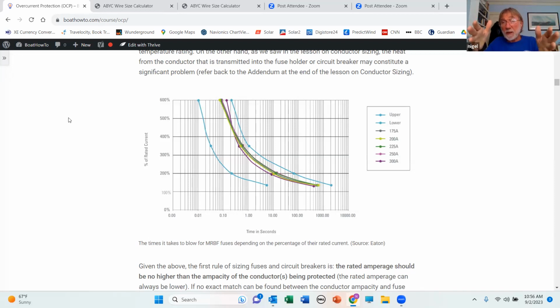Because what happens is they'll arc over, and then even though the fuse is blown, you've still got a circuit, and the fuse is not doing anything. So that maximum number of amps that it can safely interrupt, that's the AIC rating. The first fuse, the main fuse coming from batteries, if we have a relatively small lead acid battery bank, needs to have an AIC rating of 5,000 amps.